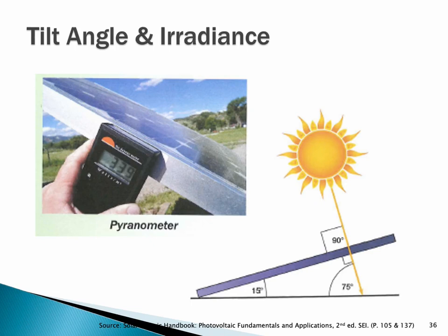Irradiance, we test irradiance with a pyranometer or irradiance meter. When you take your exam, when you see the word pyrometer, that's an irradiance meter. We're going to get those out as soon as we get a little bit of sunlight during class time. But nonetheless, when we take an irradiance meter, the meter collection window will be at the same plane as the array, so that the meter is seeing the same sun that the array is seeing.